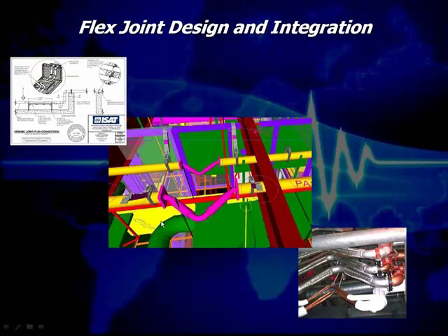The next thing, another service that we provide, is flex joint design and integration. We do this a lot, where we'll design the flex joints at those seismic joints, for example, and then we'll integrate those designs into the model. We have a project currently that I don't want to name here in Northern California that has very substantial movement at the joint, so we had to design some very specific joints for it. This is not it, but joint design is an art and a science in and of itself. So we can size the flex, and then we can also integrate the bracing and everything in order to complete that joint within the model itself.